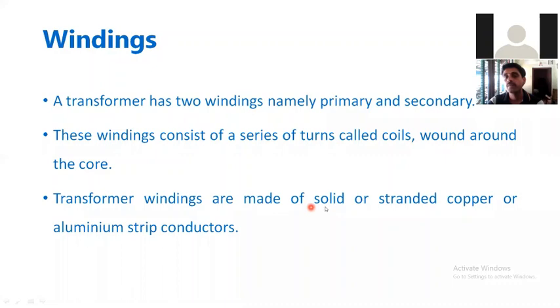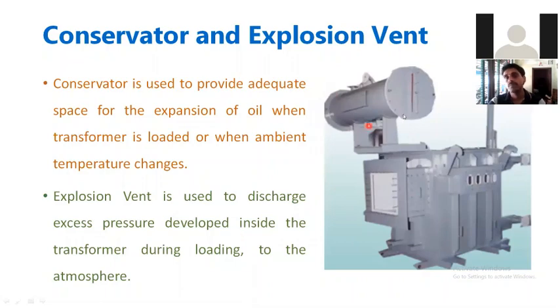Transformer windings are made up of solid, stranded copper or aluminum strip. That's what we have seen. So this is the conservator. What is the use of the conservator? To provide adequate space for expansion of the oil. Oil will be there inside the tank. The oil's main purpose is cooling and insulation. Whenever the temperature in the winding increases, the oil expands. When the oil expands, there should be some room to expand. Therefore, the oil goes to the conservator through the pipe. To this conservator, the oil will move. So this is the conservator.